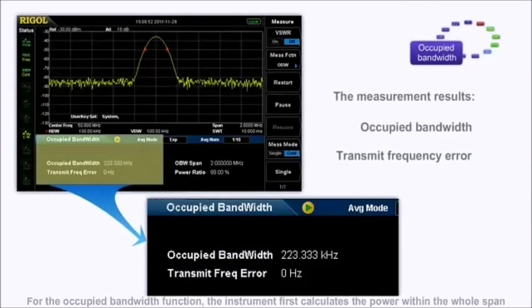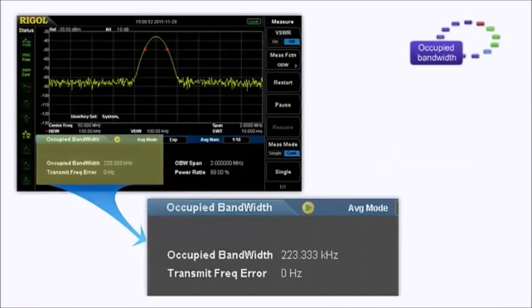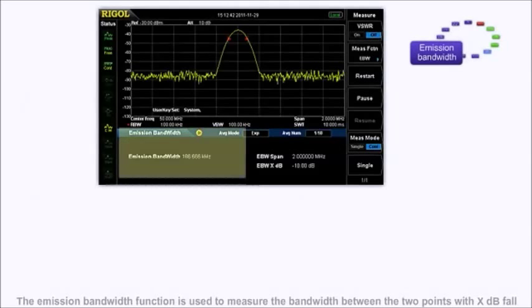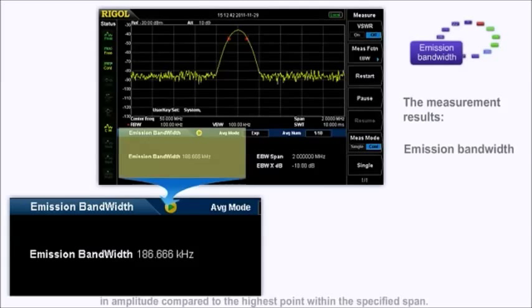For the occupied bandwidth function, the instrument first calculates the power within the whole span and then calculates the bandwidth occupied by the power according to the specified power ratio. The emission bandwidth function is used to measure the bandwidth between the two points with XdB fall in amplitude compared to the highest point within the specified span.